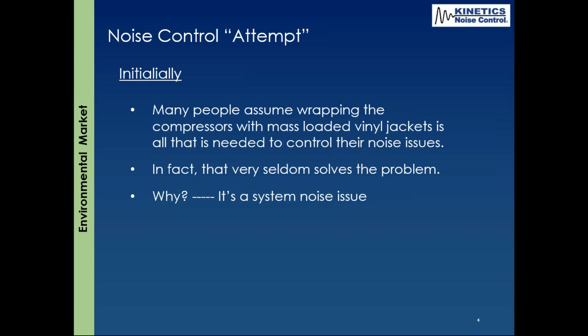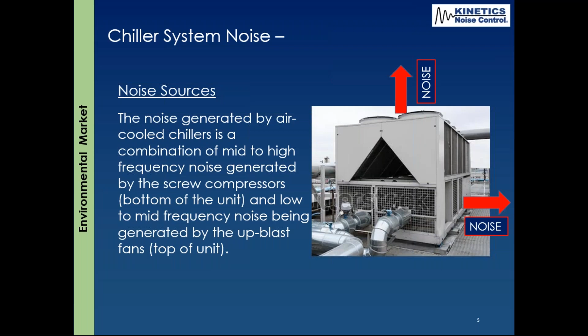Why? Because it's a system noise. For those of you that participated last month, the system noise, to remind you, is twofold: it's both the screw compressors at the bottom of the unit radiating mid to high frequency whining noise, and the upblast fans generating mid to low frequency noise. You have to take it all into account. Addressing one does not always — and very seldom does it — solve the problem.